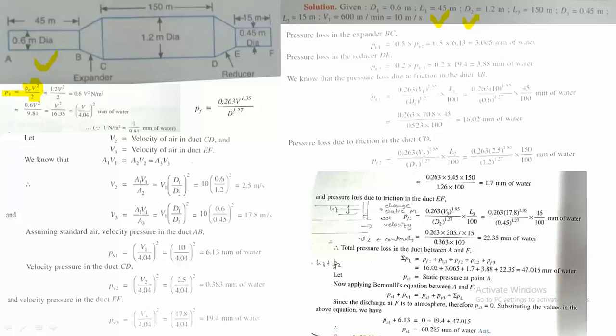If we consider only air passing through, taking the density of air as 1.2, then PV = 1.2 × v²/2 = 0.6v² Newton per meter squared. So we can say 0.6v² N/m² is the dynamic pressure — this pressure is generated when this velocity becomes stagnant, assuming no losses.